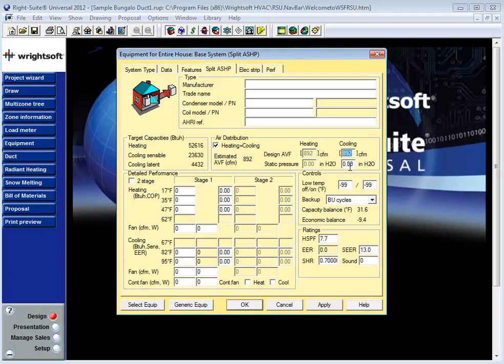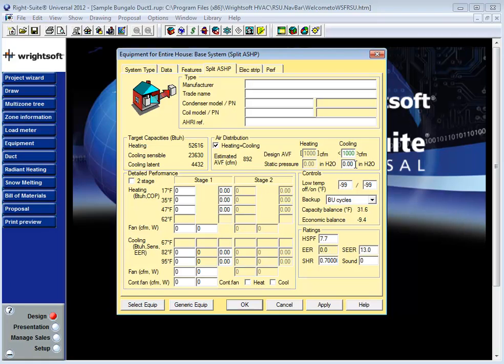If I know for example that I'm going to be moving a thousand CFM through this system I can override this field here or enter the information in this field here by using the F8 key and entering a thousand CFM. Now I'm still going to be responsible for in this case estimating the static pressure at which the fan that I'm going to choose will be able to deliver that thousand CFM.